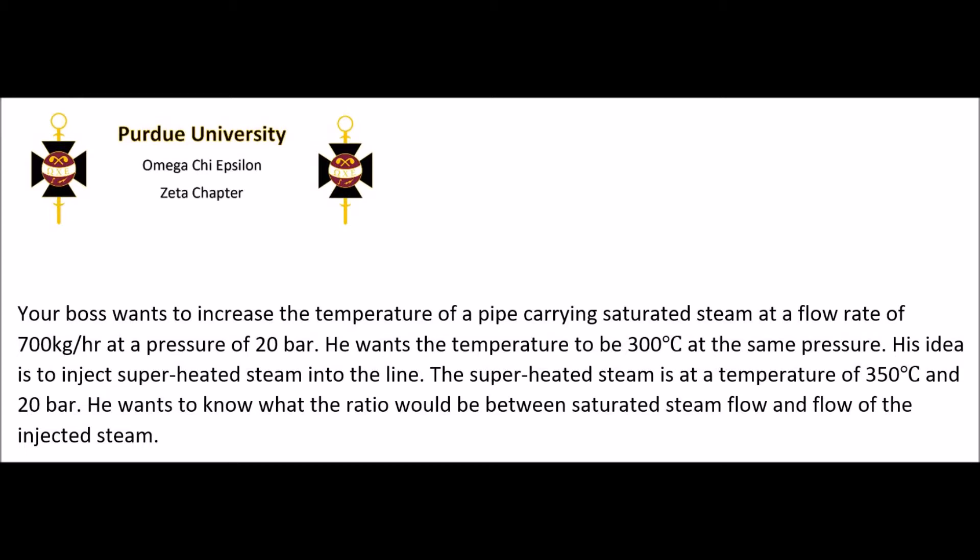Your boss wants to increase the temperature of a pipe carrying saturated steam at a flow rate of 700 kilograms per hour at a pressure of 20 bar. He wants the temperature to be 300 degrees Celsius at the same pressure. His idea is to inject superheated steam into the line, and the superheated steam is at a temperature of 350 degrees Celsius and a pressure of 20 bar. He wants to know what the ratio would be between the saturated steam flow and the flow of the injected steam.